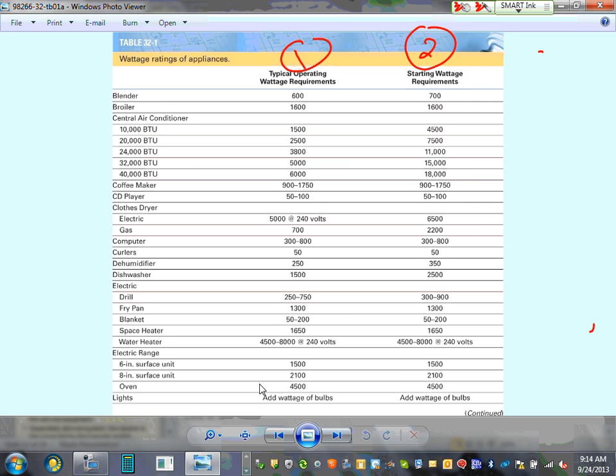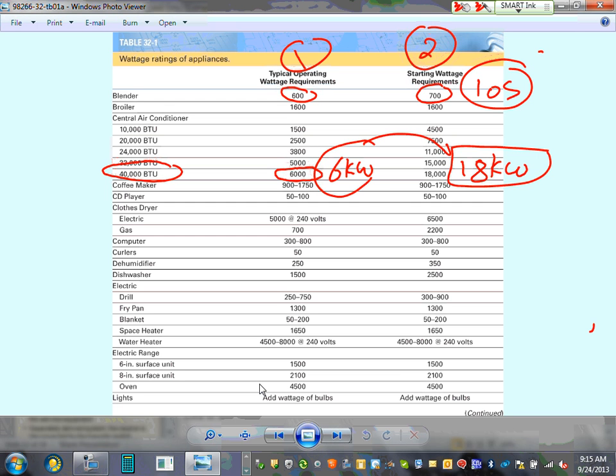For example, a blender has 600 watts of running load. When you start it, for only 10 seconds, not forever, it will be seen as 700. Can you guys see the difference? Look at the AC units. If you have a 40,000 BTU, the largest one you can get, it will be seen as 6 kW. Look, can you guys see the difference? It goes from 6 kW to run, to 18 kW to start. See why starting the equipment is typically 3 to 6 times more oomph than to run it.